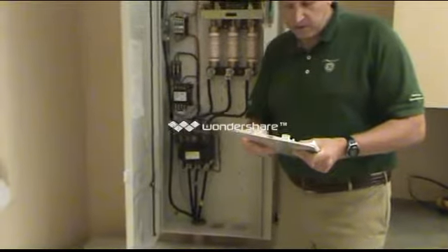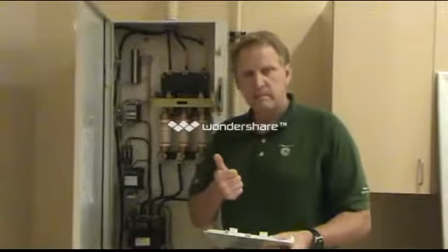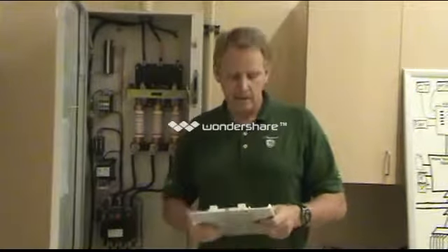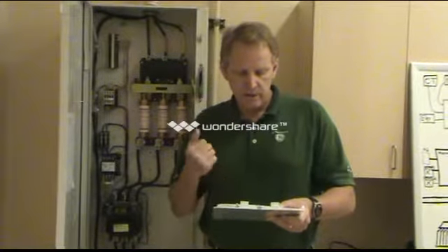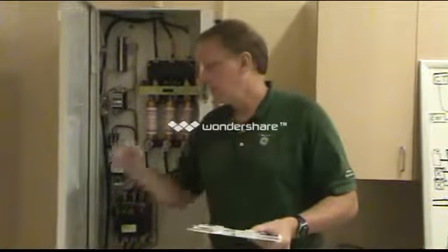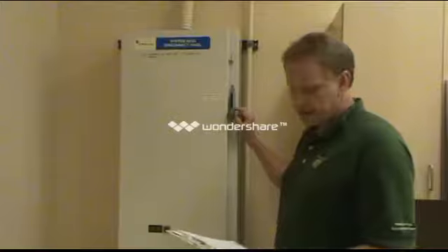All right, so has a power filter or regulator been installed? Step 12, there's a lot that can be there. It could be an old transductor, an old power tech. It could be a filter on a new vascular system. It could be another style of filter. I've seen some filters from RadX. Basically, it's going to be a big box about so big, sitting upstream from the A1 panel. In this case, I know that there is nothing. It's all good. If there was one, we need the manufacturer, the amperage rating, and the location. All right, so can the panel be locked and tagged out? GE A1 panels, I have no issues with. Pretty much, yes, it can be locked and tagged out.